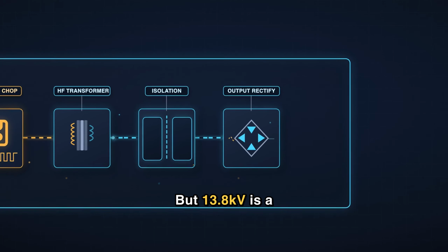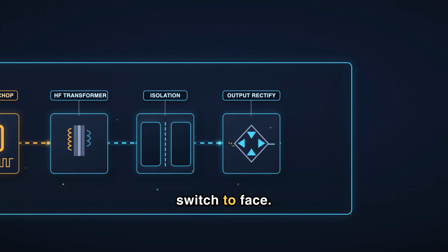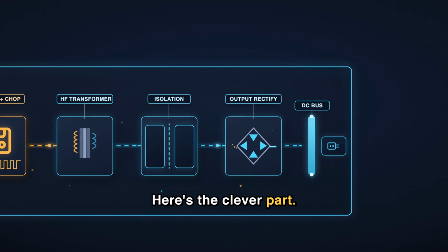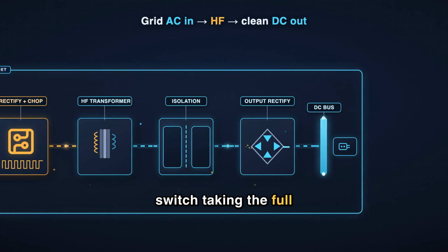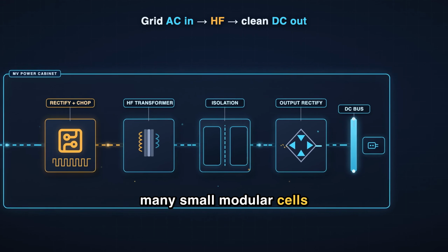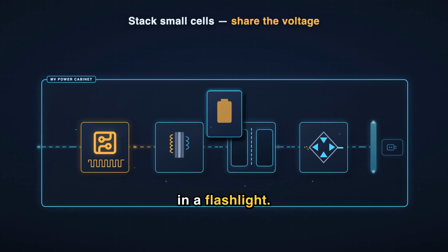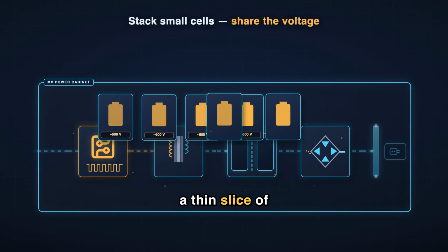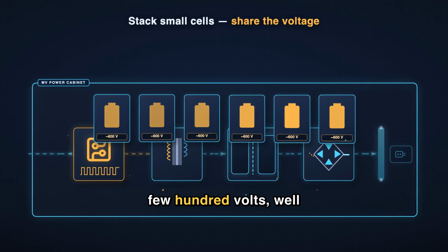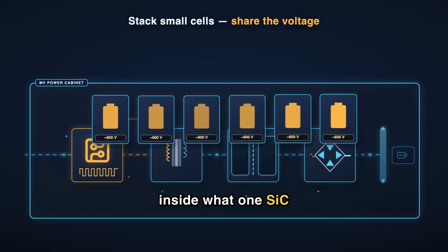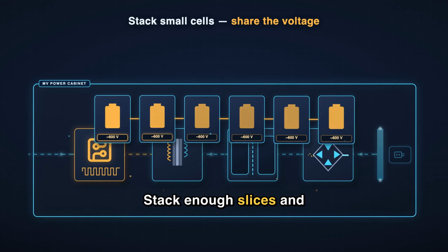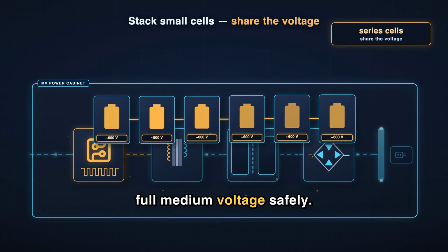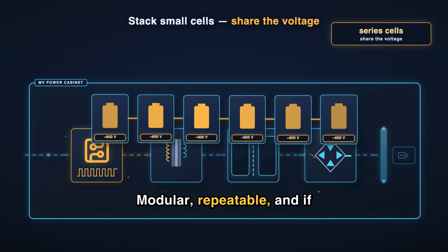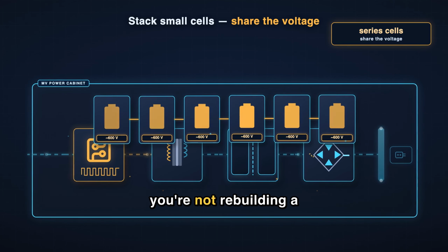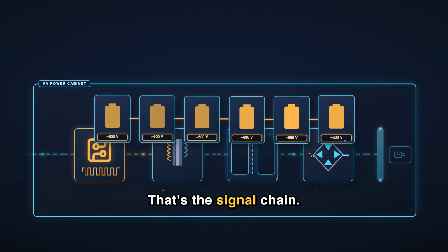But 13.8 kilovolts is a lot for any single switch to face. Here's the clever part: instead of one heroic switch taking the full hit, the box stacks many small modular cells in series, like batteries in a flashlight. Each cell holds only a thin slice of the total voltage, a few hundred volts, well inside what one silicon carbide stage can handle. Stack enough slices and together they span the full medium voltage safely. Modular, repeatable, and if one cell needs service, you're not rebuilding a monolith. That's the signal chain.